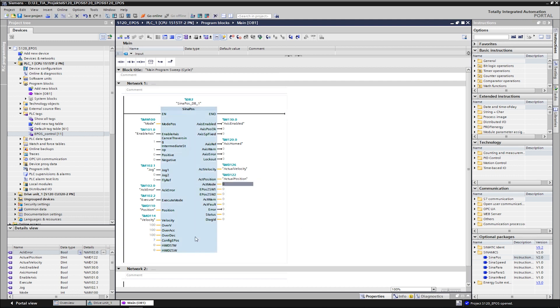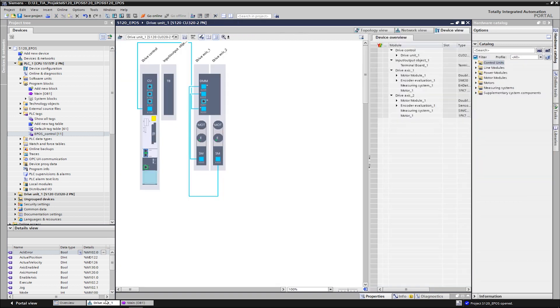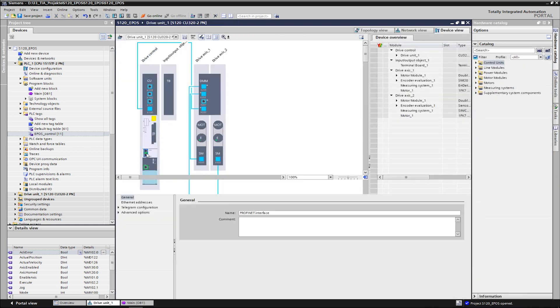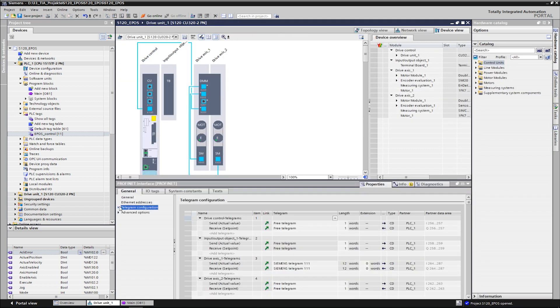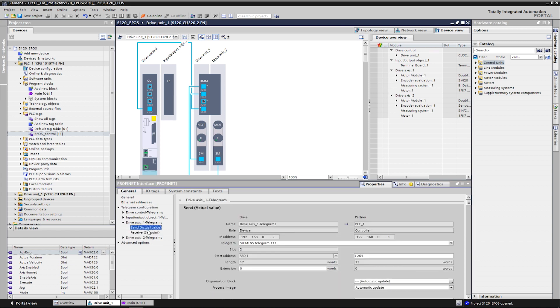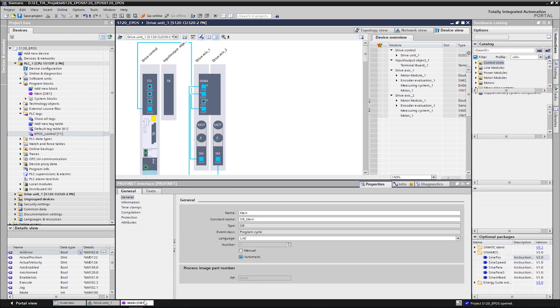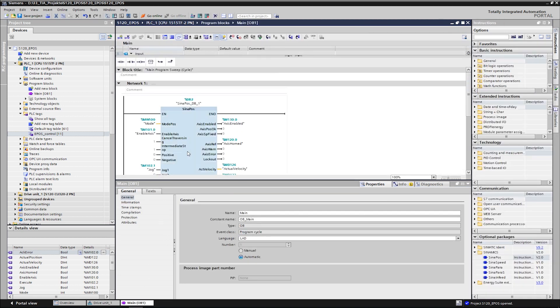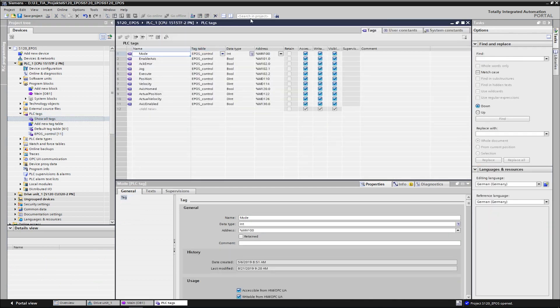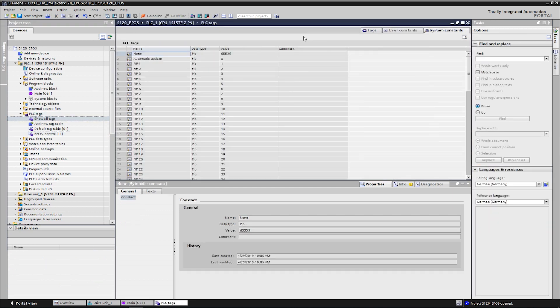Then we come to the inputs that are important for the correct operation of the communication. We have to inform the block about the hardware ID of telegram 111, with which the drive block should communicate. The hardware IDs are automatically assigned by the PLC when the peripherals are networked. We find the hardware ID of the telegram, for example in the telegram configuration of the drive, or in the system constants of the PLC.